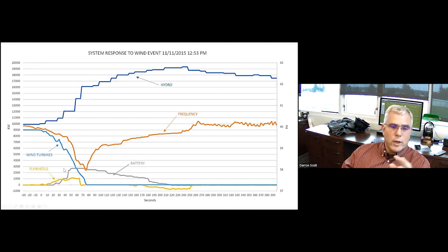This was just shortly after everything was installed with the flywheels and all, and we're going along just fine. We had 19 megawatts on our system, about an average load day, nice winds coming, 9 megawatts of wind, everything stable, 10 megawatts of hydro, working together great. And all of a sudden, the wind just goes away over a matter of seconds. It wasn't that the wind power tripped off or anything like that, it's just the wind was blowing 25 miles an hour, then it went to blowing nothing, in just a matter of seconds, and stayed that way. We don't get that very often, but it can happen up here.